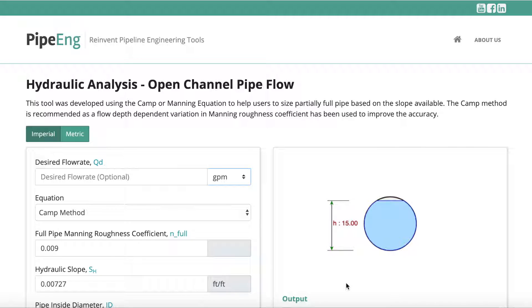For open channel flows, typically we use Manning equations to evaluate the hydraulic performance. In the 1960s, Mr. Tr Camp proposed a different method modified from Manning equations to improve the accuracy when it comes to open channel pipe. For this tool we offer both options, but we recommend the Camp method over Manning method because the Camp method has considered the flow depth and that will improve the calculation.